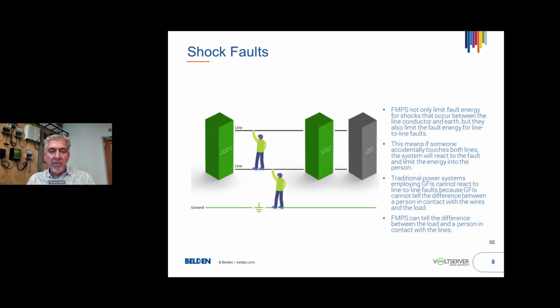These systems, fault-managed power systems, actually detect the difference between a load device at the output of the receiver drawing a load and a person that might be touching the lines, and they'll interrupt power if that person touches the lines. All these things are critical to being able to install like a class 2 circuit as we know now. So those rapid installation techniques in a commercial environment that doesn't require conduit, just like a PoE cable or Ethernet cable.